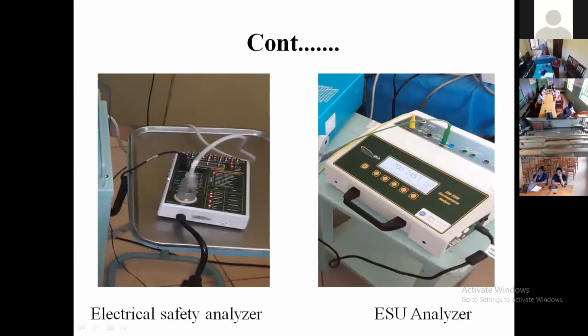Continuing, you can see here, this is the electrosurgical electrical safety analyzer. This analyzes electrical safety. So during the maintenance, we do electrical safety checking to see if the equipment is behaving according to our checklist.